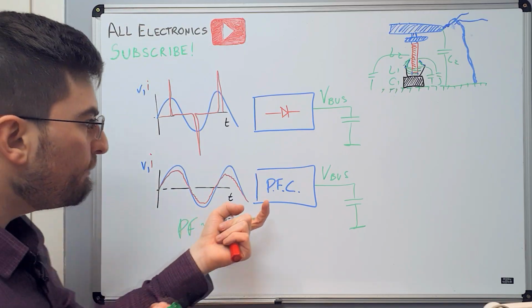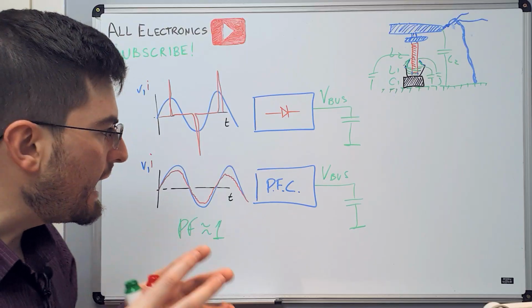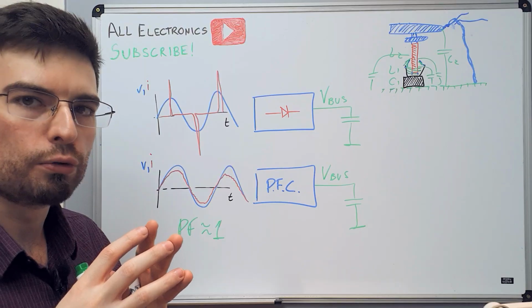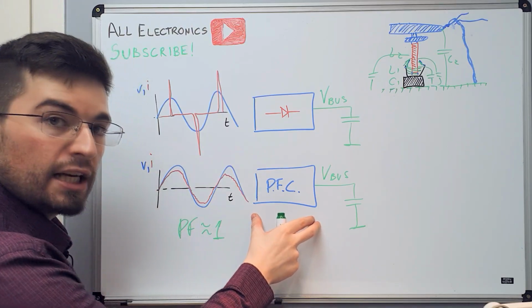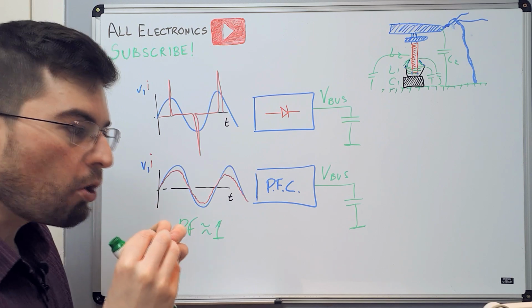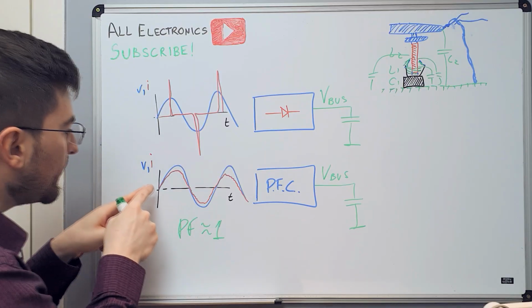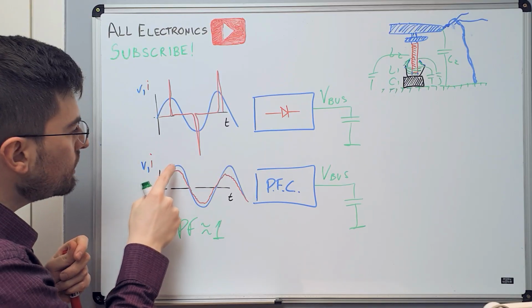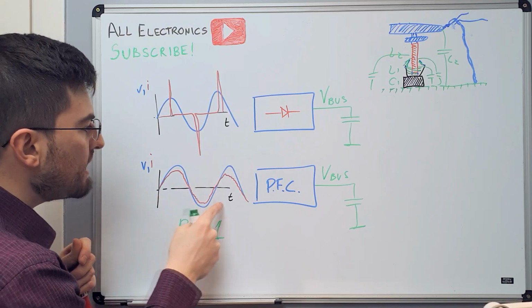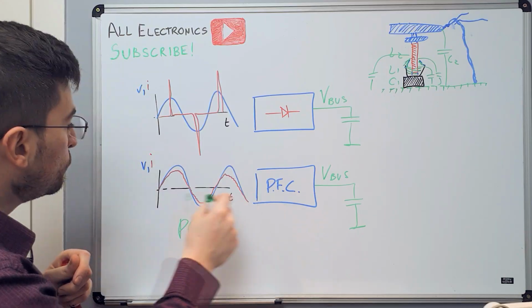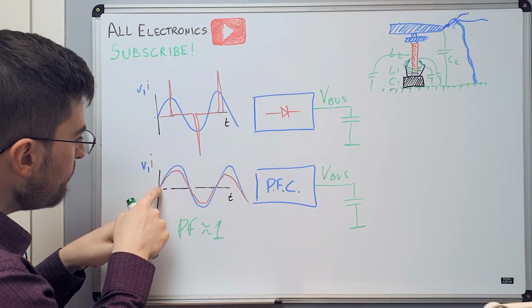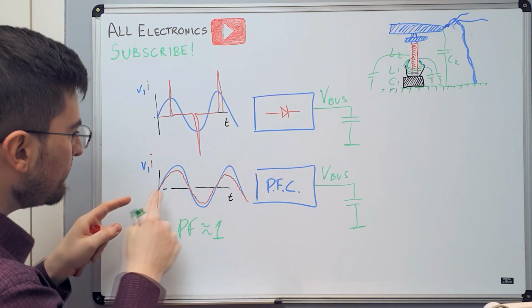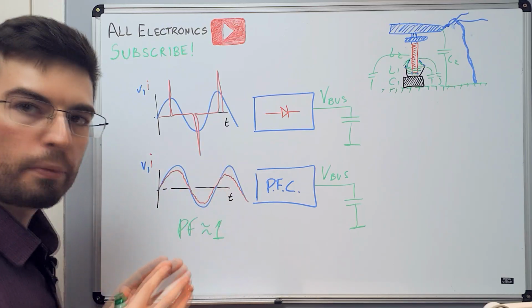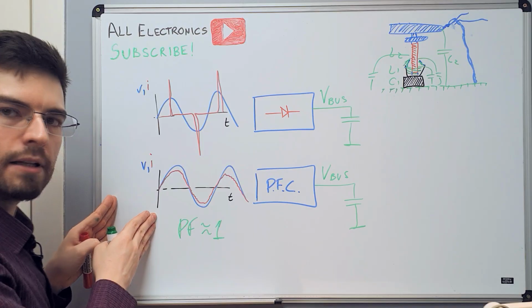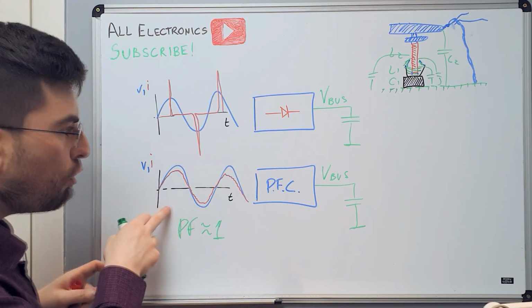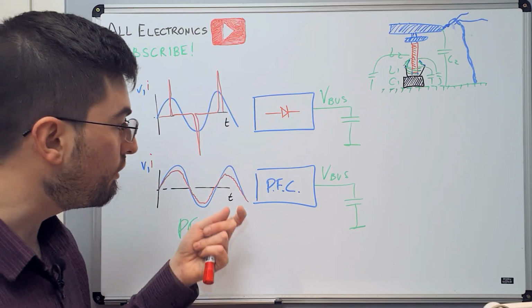The PFC is an electronic circuit that is actually mimicking a resistive load. That's very interesting. It has power conversion electronics using an algorithm, an electronic way of creating artificially a sinusoidal current in the input synchronized with the voltage. So it uses power electronics to take energy from the mains even with very small currents, and modulates this current to follow the sinusoidal profile. So for the mains, the power factor is very high because the load looks resistive. This is the magic of a power factor corrector.